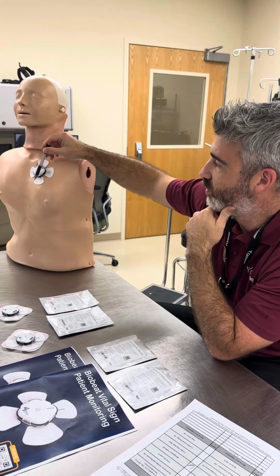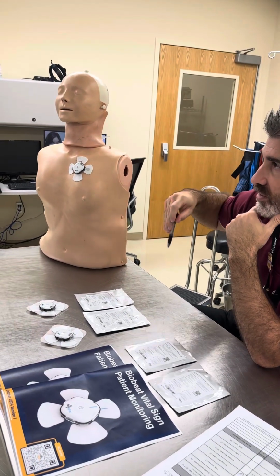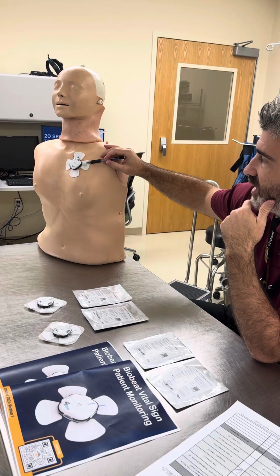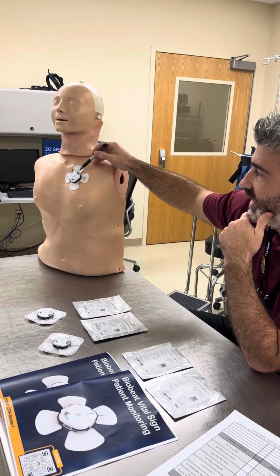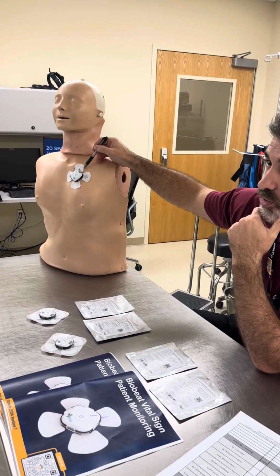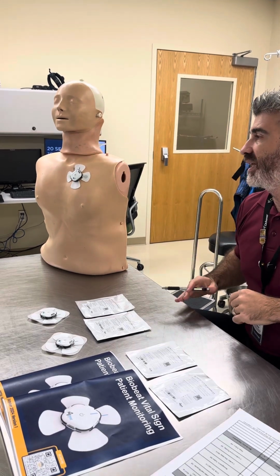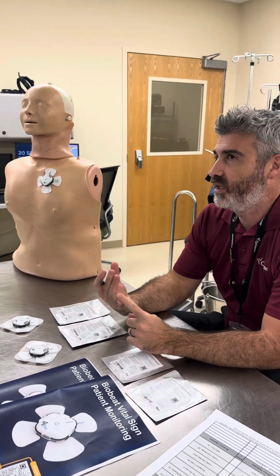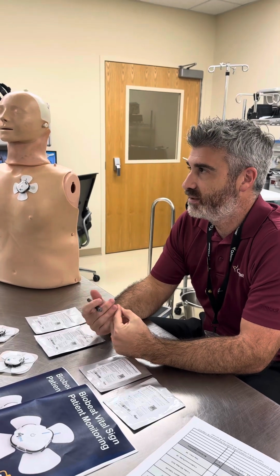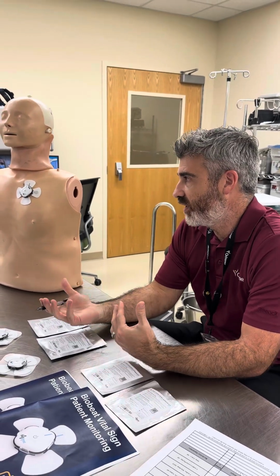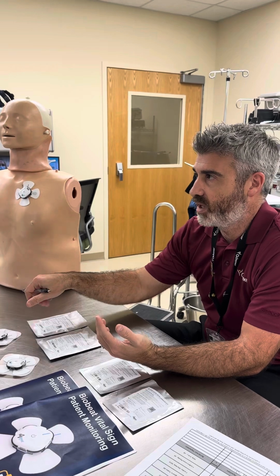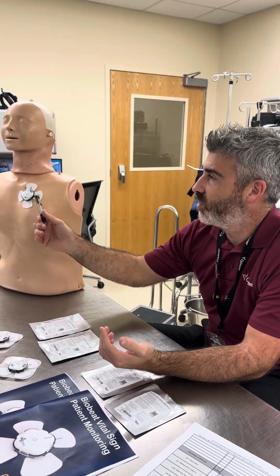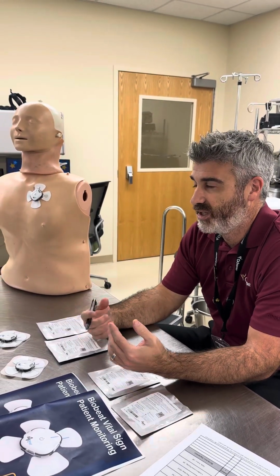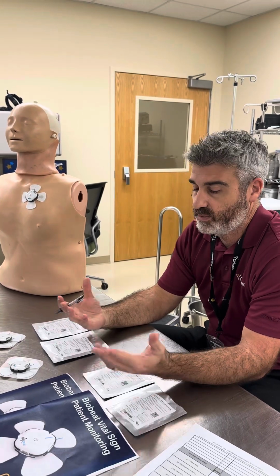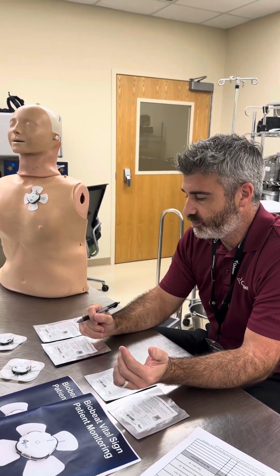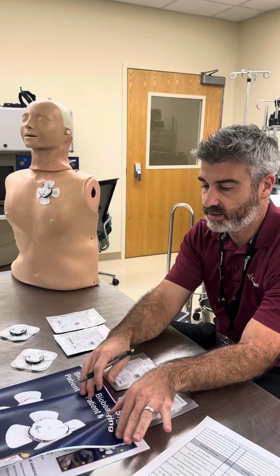This is strong adhesive on here. You can use whatever normal prep you would use, alcohol swab, whatever you guys are using for skin prep. If you have a male patient, kind of hairy, clip that hair down a little bit, do him a favor. It's a single-use device. This does not get cleaned, no CaviWipe in this. Whether a patient wears it for 8 hours or 5 days, you take it off, you throw it in the trash. Battery life on it, it does last about 5 days because it's recording vitals every 15 minutes. Pretty good life run. Again, it's just these two pieces.